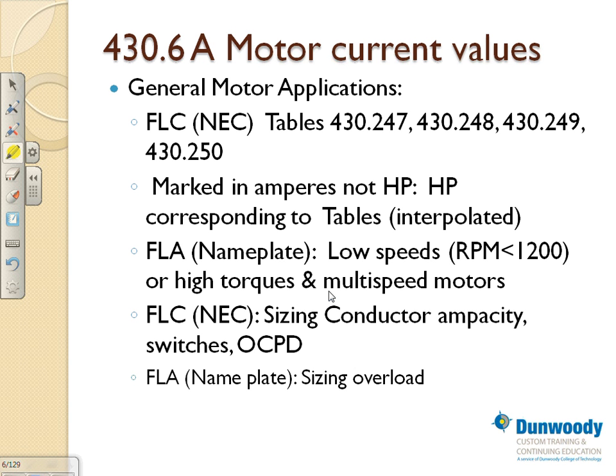And also, if you have high torque motors or multi-speed motors, these are the applications where this would be on your master exam. They will give you a motor. That's how we trick you. They say a motor is running at less than 1200 RPM. Find the disconnect for this motor. So you go to the tables, wrong. You have to use the nameplate that they give you. So it's a tricky one.